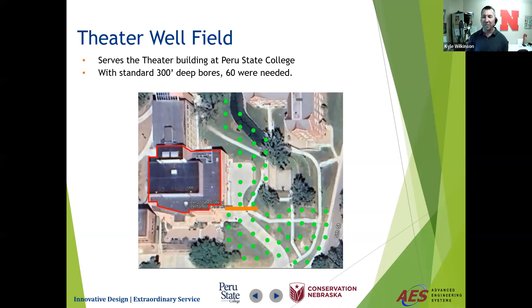We put in 60 boreholes, 300 feet deep, as opposed to TJ Majors where they were 450 feet deep. Depending on the tests and the site available, you figure out how far apart they are, how deep they are, and how many you need. 300 to 350 is kind of your best bang for your buck, if you have the ground.